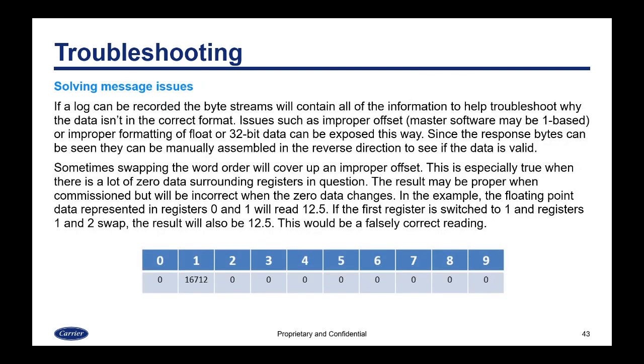If a log can be recorded, the byte streams will contain all of the information to help troubleshoot why the data isn't in the correct format. Issues such as improper offset — when the master software may be one-based instead of zero-based — or improper formatting of float or 32-bit data can be exposed this way, since the response bytes can be seen and manually assembled in reverse to verify if the data is valid.